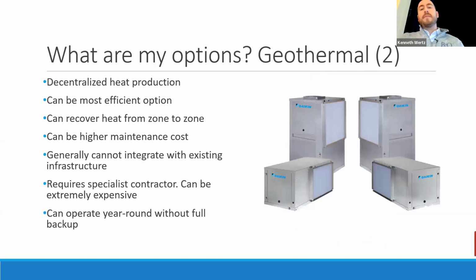But the other flavor of geothermal, rather than having that central chiller boiler that's distributing hot water, chilled water, is you can distribute the geothermal water itself within the building and then have a water source heat pump, a 1 or 2 ton unit in every room. That's often the most efficient option that's out there. You don't have those limitations on not having a high enough temperature to be able to keep the room warm. And you've got much more flexibility in that each room has its own system, as opposed to being limited by the overall central system.